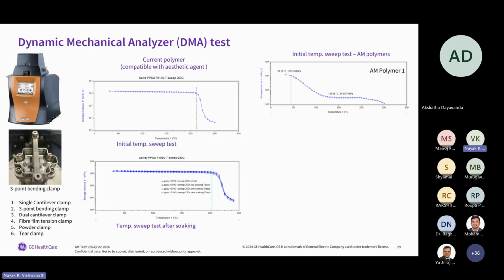The regulation says it has to be soaked for 20 minutes, and when you remove it, it should have the same behavior. But the behavior here, for us, is that we cannot have a degradation of mechanical properties. That is important for us. The polymer may not have corroded or anything like that, but it is not behaving with the same properties. That is not acceptable to us.